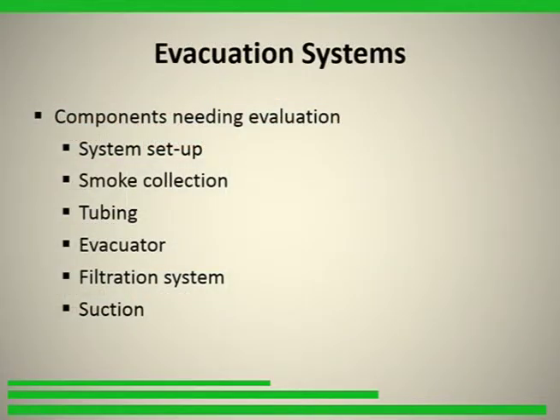The evacuation systems have multiple components to them. They have a smoke capture device, we've just talked about those, with tubing of various sizes, the smoke evacuator, which can be desktop, or it can be a central vacuum system, a filtration system, which almost always is an ULPA filter, an ultra low porosity or penetration air filter, which is used to filter the smoke that's collected, and then it returns the effluent back into the operating room, and various kinds of suction devices.